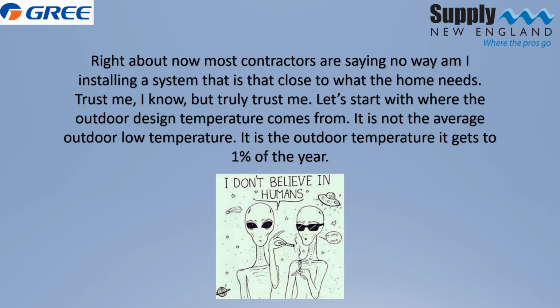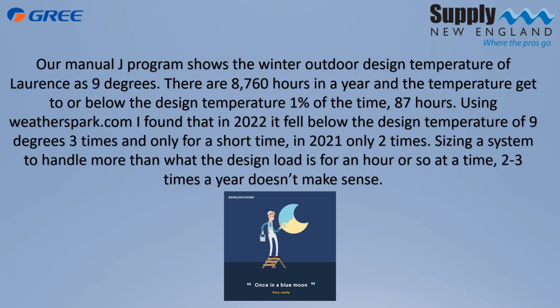First, every program, and some of them don't want to admit this to us, but they have some fudge factor in there. The next thing we have to remember is the 1% rule. That temperature only happens 1% of the year. The 1% rule means that of the 8,760 hours there is in a year, it only fell to 9 degrees in Lawrence, Mass. for 87 hours. I am who I am, so I went to weatherspark.com, and I found that in 2022, it fell below 9 degrees 3 times. And those 3 times were for very short periods of time. And in 2021, it only happened 2 times.